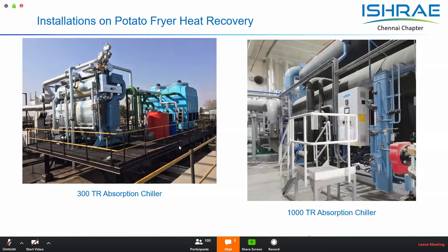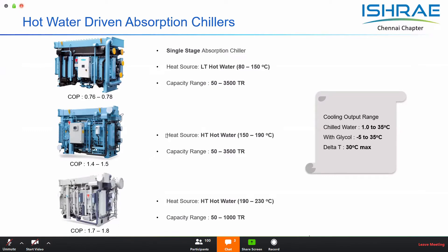Hot water can also be used as a heat source for an absorption unit. Hot water is available at various temperatures; when temperatures are 80 degrees Celsius and above, we can use a single-stage absorption chiller to generate cooling. Capacity ranges can be from 50 to 3,500 tons. Importantly, today there are technologies available that can utilize water at temperatures lower than 80 degrees Celsius as well.